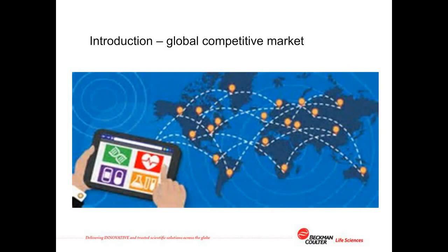As the pharmaceutical industry seeks to reduce the number and associated costs of quality control laboratory tests, reliance on results from TOC analyzers for product release is becoming more attractive, especially online TOC analyzers. The International Conference on Harmonization — the ICH — is an expert working group with representation from the United States, European, and Japanese pharmacopoeias. In their harmonized tripartite guideline ICH Q2, titled Validation of Analytical Procedures, they outline characteristics for consideration during validation of analytical procedures submitted within the European region, Japan, and USA. This presentation discusses how these characteristics may be applied to online TOC analyzers to enable them to provide release test data for water for injection and purified water.